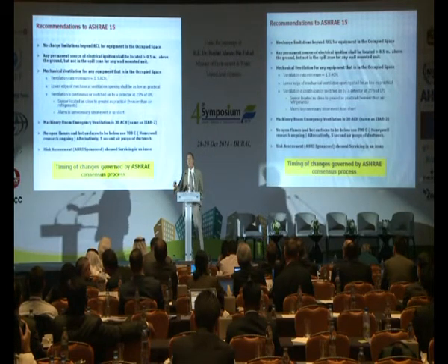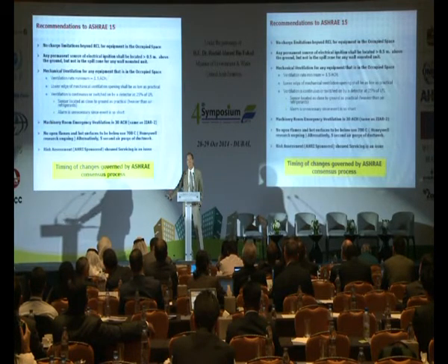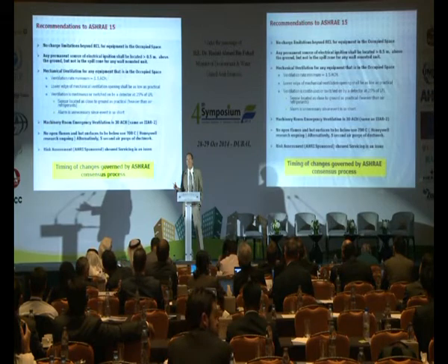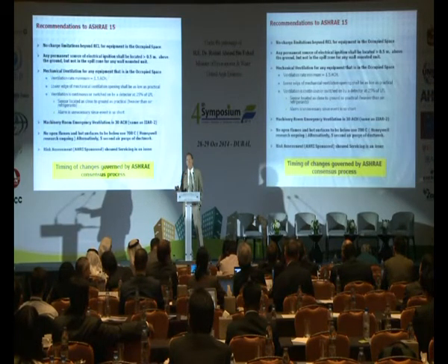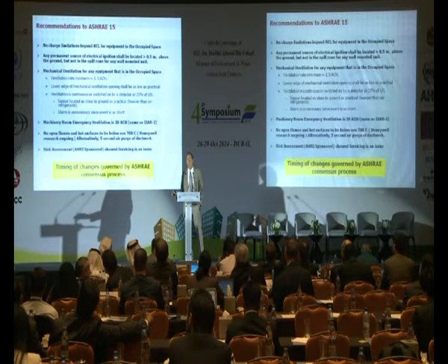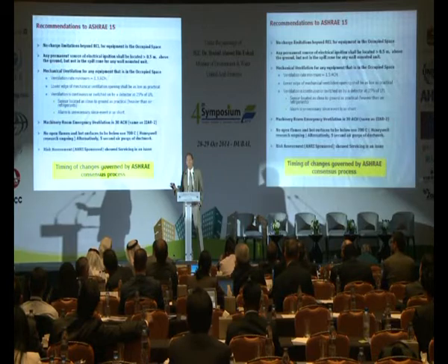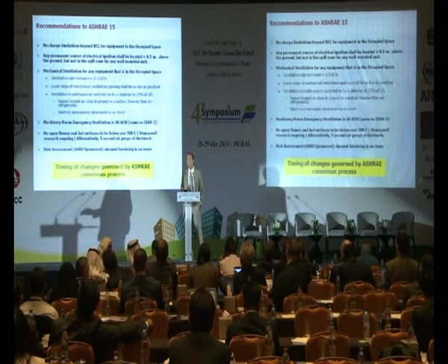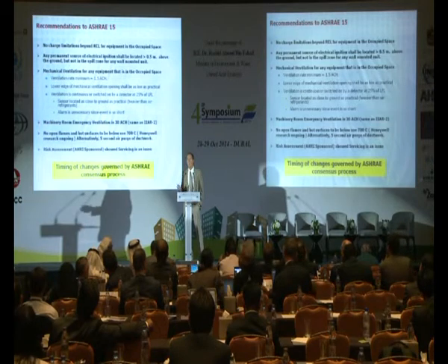Mechanical ventilation. We talked about putting the exhaust air as close to the floor as you can. Many systems are fed by VAV systems, and so we want to make sure that that ventilation air doesn't get shut off. We want to keep it running. We want to have 1.5 air changes an hour. That will exhaust the refrigerant in minutes, and so that's a very, very easy thing to accomplish in a safe installation.